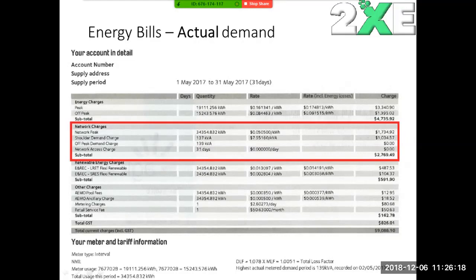One of the main things to point out is that this is an actual demand tariff, so you'd expect peak, shoulder, and off-peak, but we're actually outside the annual peak period since we're in May. So what is the peak demand we reached? Every electricity bill highlights your peak demand, appearing in a sentence like this. Down the bottom right, the highest actual metered demand for the period is 139 kVA, during the period when costs are highest. It tells you the demand you reached, and most importantly, the date and time you reached it. That's important because it can help identify what was going on at your winery at that time, what's leading to these spikes in demand, which is really important for developing strategies to reduce it. That's an example of an actual demand tariff electricity bill.